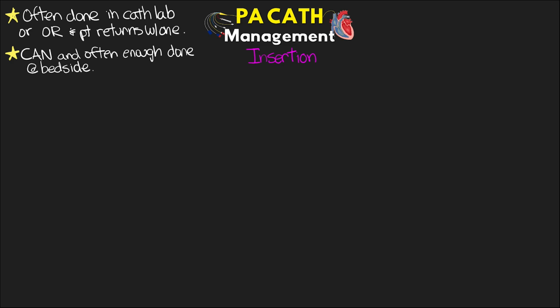Typically, they are going to be watching the monitor as they're floating the Swan, and one thing that's really helpful is you can put the monitor into either the wedge setup or look for a larger setup for PA catheter insertion. Basically this puts your PA pressure nice and big on the monitor. And remember those waveforms, what they look like, and the order that we're going to go through them. When we first get the catheter in there, we start off with the CVP, ending up in the RA, so we're going to see our RA CVP waveform like we see here.